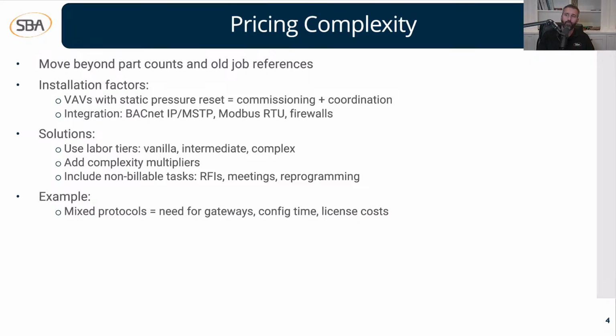We live in a world of protocol mashups. If you look at buildings today, sometimes you have a legacy control system with proprietary communications that can't talk to anything but its own vendor. Or you might have a LonTalk building that was popular in the 2000s. Today everybody's going towards BACnet, mostly BACnet over IP and often BACnet MSTP. You might even see a Modbus type of job too.